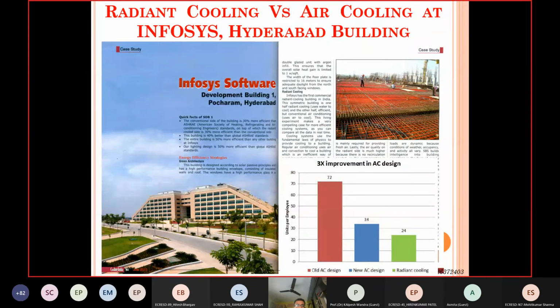Right. And one such system has been implemented in the Infosys building in Hyderabad, and they have two symmetric divisions of the building. One of them is cooled with a conventional but highly efficient system of air conditioning. And in the other one, radiant cooling is implemented, and as the building is being built, this is how the lines for the cooling water are laid in the flooring, that is shown here.